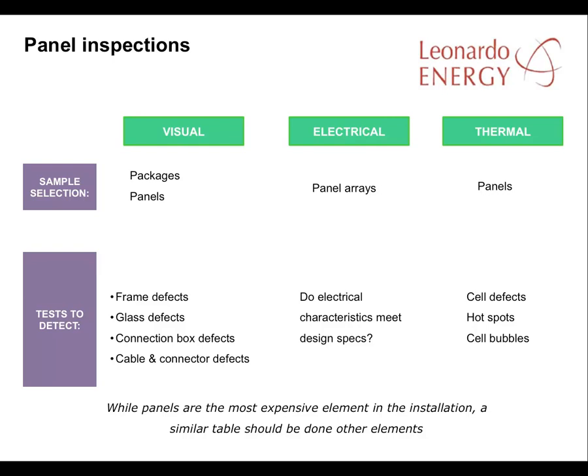A range of specifications of different elements will be needed as part of the quality assurance process. Here we're using panel inspection as an example because the panels are the most expensive element in the installation. It would be impossible to inspect all of the modules delivered to a big plant, so you pick out some samples. These should be subjected to visual, thermal, and electrical inspection. The visual inspection is to detect frame defects, glass defects, as well as connection box and cable or connector defects.